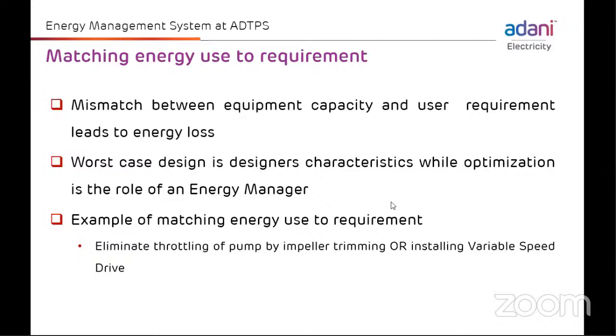I can quote one example of matching energy use to requirement: because of this extra margin, many times we need to throttle the pump discharge to match our requirement. In that case, operation optimization can be done either by throttling, by impeller trimming, or by installing a variable frequency drive on that motor. Accordingly, we modify the process or equipment so as to reduce the energy use by that particular equipment.